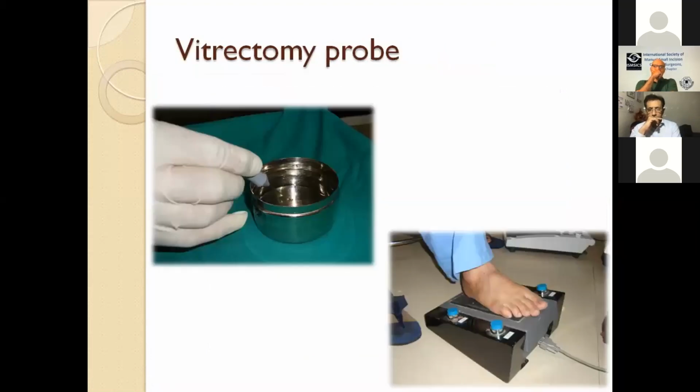And the vitrectomy probe sometimes will not work when we start working. That is because of clogging with visco or vitreous. So at the end of each vitrectomy surgery, whenever I use it, I clean it myself by dipping the probe into the BSS and pressing it with the vitrectomy on once and vitrectomy off once.